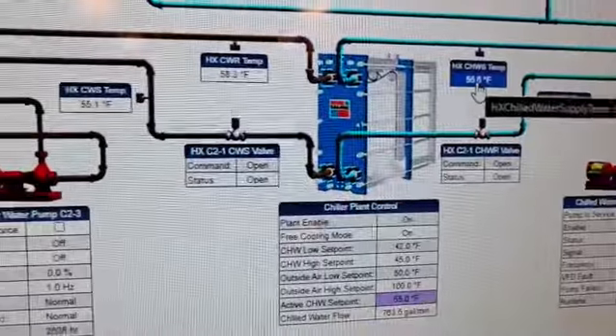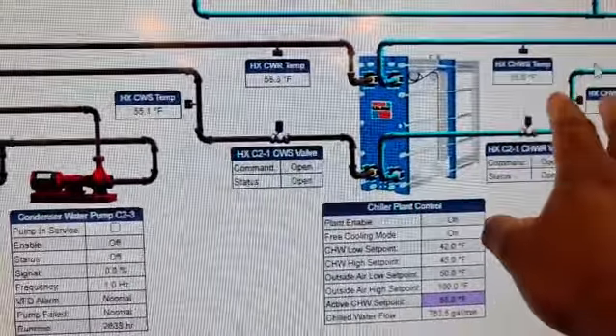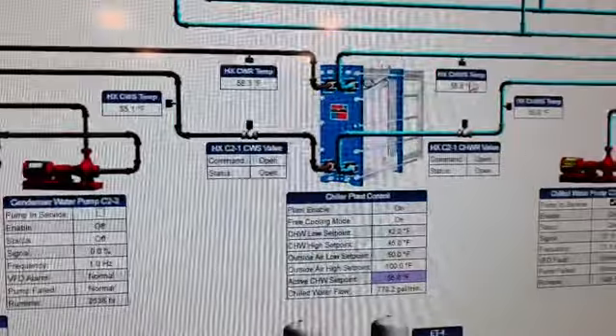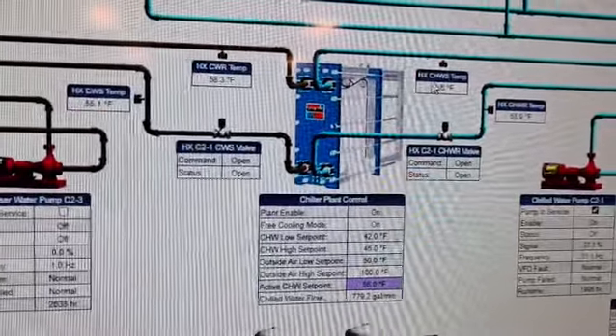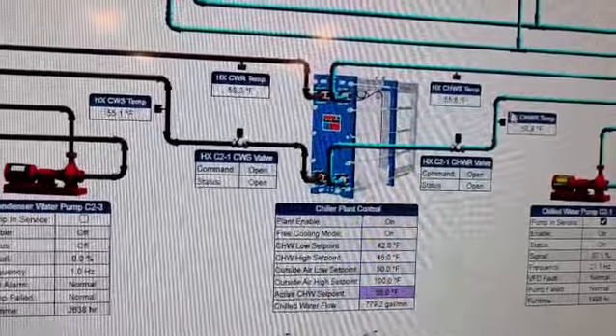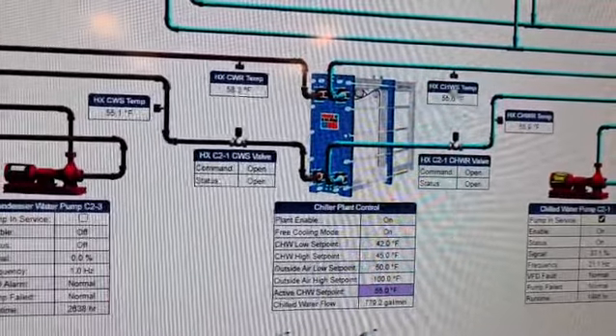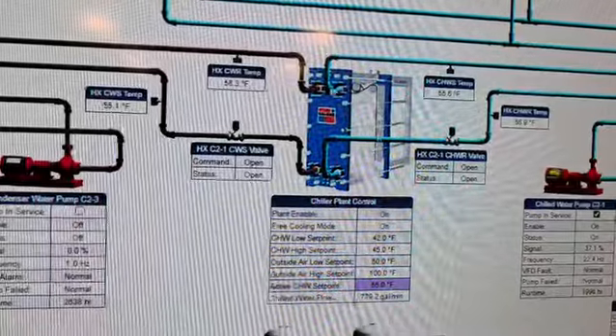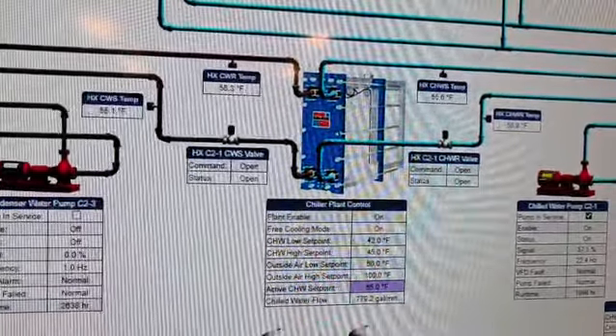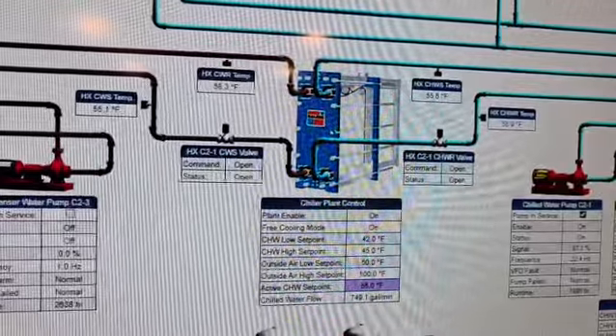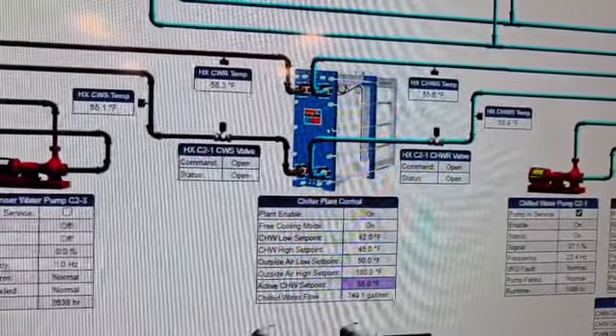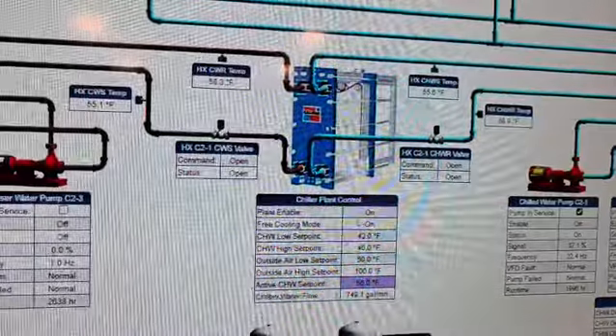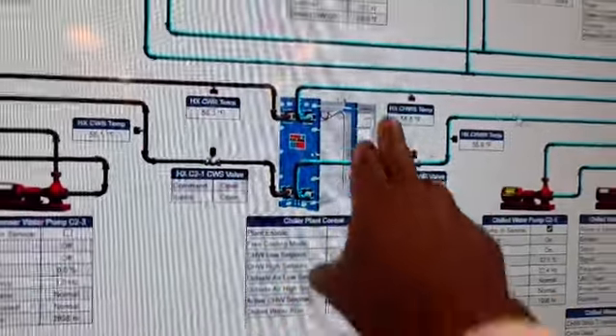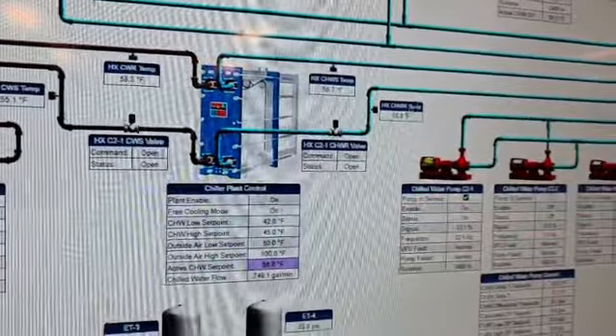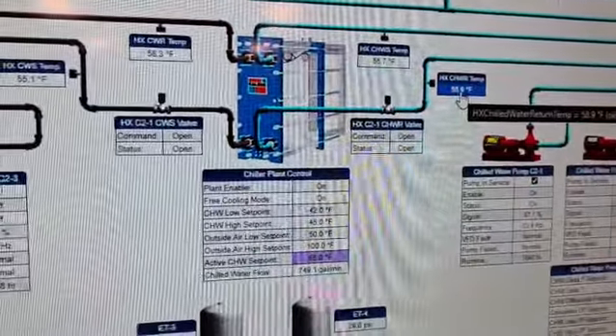Come back again, what is the difference between this and this? Right there. Explain the difference again between this and this. Right, it says right there. You see this? Chilled water supply. What is it again? Chilled water return. This is the water that leaves the heat exchanger and goes into the building. Every unit that is open for cooling will get this water, and then it will come back. So this one brings back heat. It comes back hotter. I see. That's why the return is hotter.